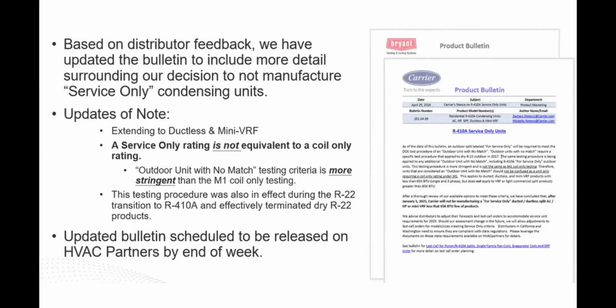The first challenge is that in order to comply with energy code in like 47 states, you have to have a SEER rating, which comes from AHRI. And the only way to get a SEER rating for most stuff is to have a matching indoor and outdoor coil. So if we have these service only units and there's no matching coil associated with them, which there's not, then you can't get a SEER rating and you can't comply with energy code. So because of that, the manufacturers are not building them.